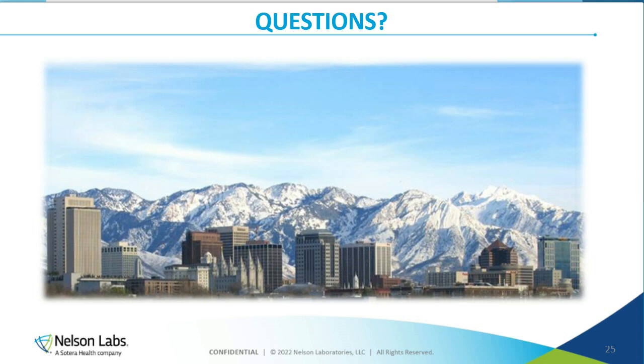So really, we should look at the device in the aged state and see if there is any concern. As I said, I don't want you to do additional testing, but we always recommend also running a comparative cytotoxicity test on the aged device. Because it's so sensitive, anything that could potentially happen will happen there. As we all know, this test is prone to failure. So if you have the T0 and the aged device, and you see with cytotoxicity that nothing is changing, and there are no obvious changes by visual inspection, I think that's where we should stop right now.